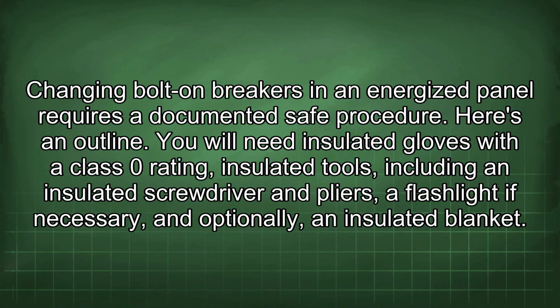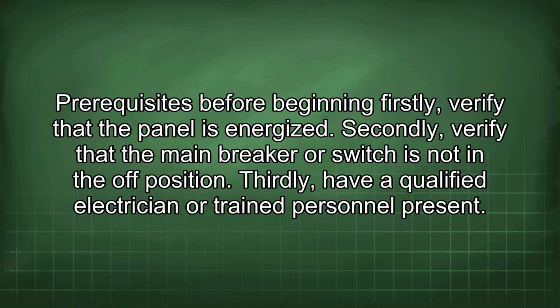Changing bolt-on breakers in an energized panel requires a documented safe procedure. Here's an outline. You will need insulated gloves with a Class 0 rating, insulated tools, including an insulated screwdriver and pliers, a flashlight if necessary, and optionally, an insulated blanket. Prerequisites before beginning: firstly, verify that the panel is energized.